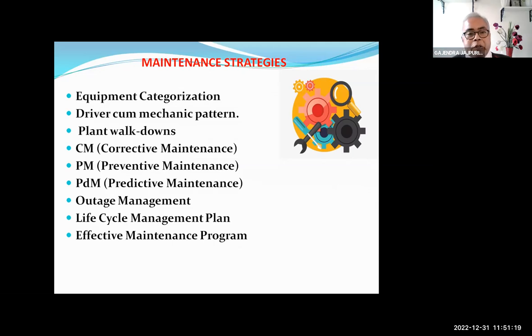Then ferrography of the lubricating oil also gives an indication of what has failed inside. Or thermography, which indicates temperature rise. In electrical equipment, thermography is a technique utilized for finding loose connections. Or dissolved gas analysis, about which I just shared an incident, and insulation checks using tan delta and capacitance tests.